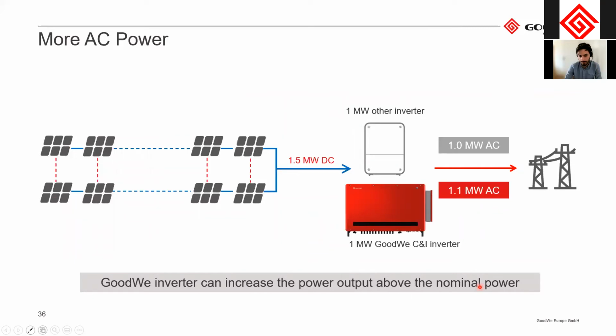As I mentioned before, also in the residential segment, our C&I inverters also have a feature called AC overloading. This means that they can produce 10% additional AC power compared to the nominal power rating. So in this case, if you have a PV system here producing 1.5 megawatt of DC power, in a normal case, let's say a 1 megawatt inverter would at max be able to produce 1 megawatt of AC power, capping this at 1 megawatt. Our inverter, however, could then operate at 1.1 megawatt, even if it's rated for 1 megawatt of AC power. So you get a bit more AC power for the same amount of inverter, basically.